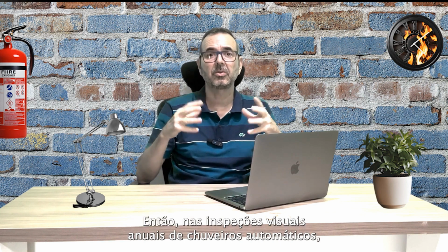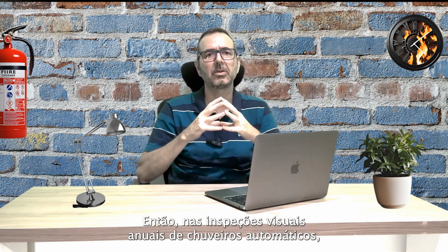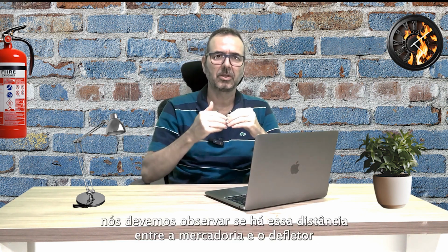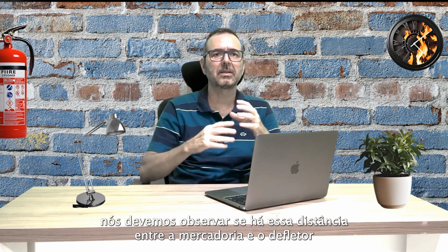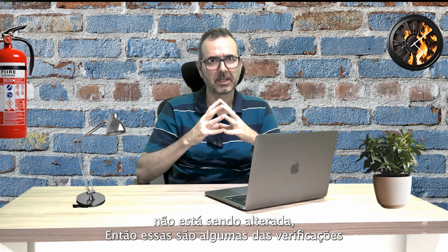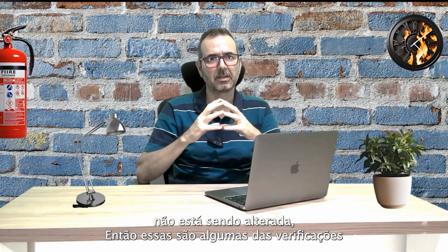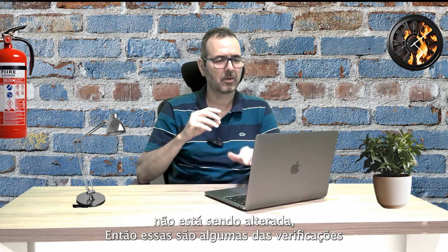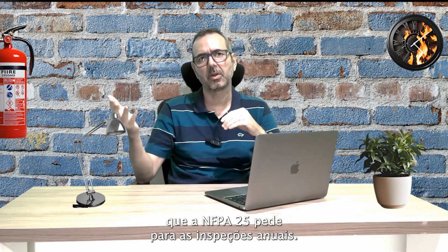During the annual visual inspections of automatic sprinklers, we must observe whether the distance between the merchandise and the deflector is not being altered. These are some of the checks that NFPA 25 requires for annual inspections.